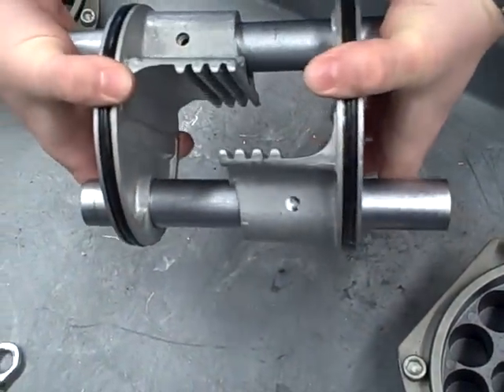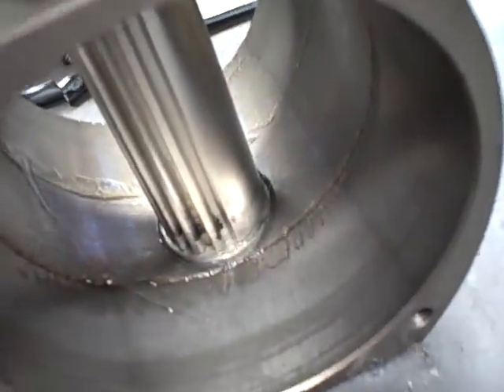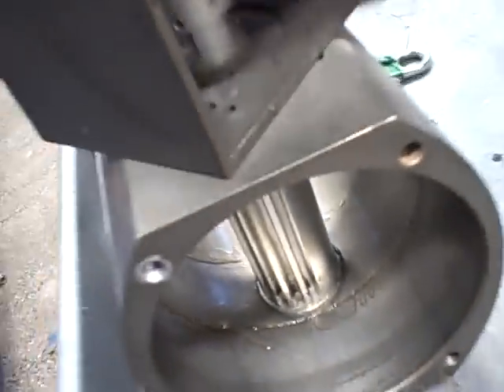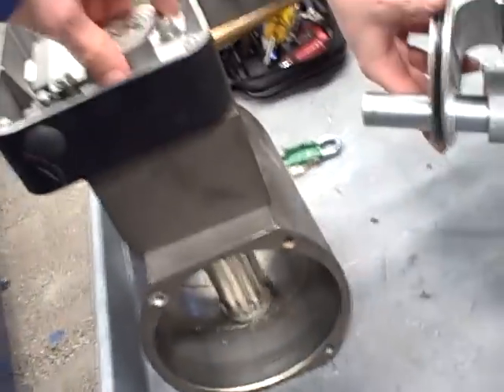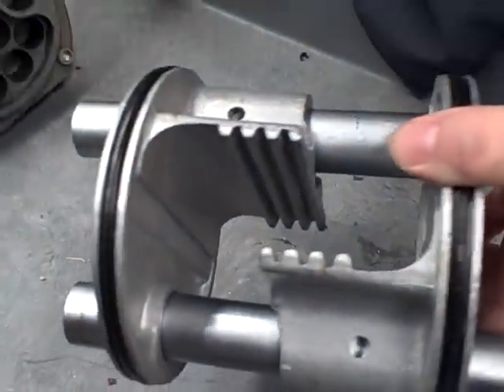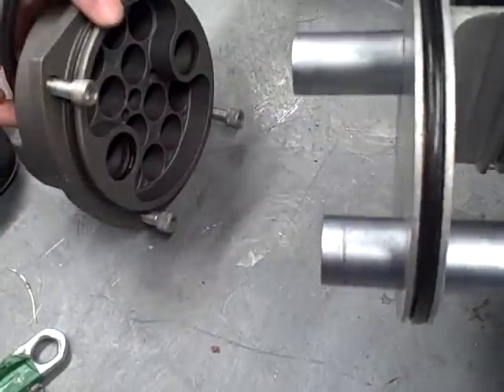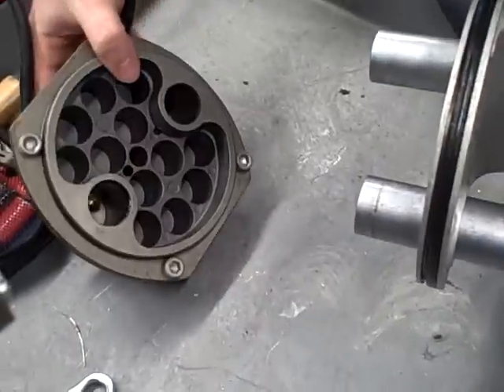This is the actual rack, and the pinion itself is inside here. As the actuator turns this piece, it moves the pinion inside — as that grabs, it moves it inside and out, which then changes the air on one side.